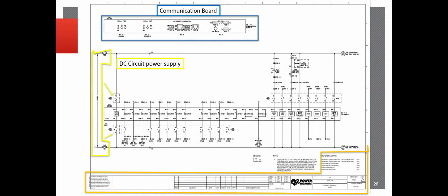To the left of the schematic, we have the DC circuit power supply. This is what you do before you even turn anything on. You verify the power supply is the correct voltage for one. You've got to see what the relay is rated for. In this case, you verify the relay is rated for 125 volts DC. You verify in the schematics that you're going to be receiving 125 volts DC, and then you will go and verify that it is in fact 125 volts DC at the breaker cabinet before you even turn anything on. You'll measure it, verify it, and then you'll hook it up and put power to the relay.